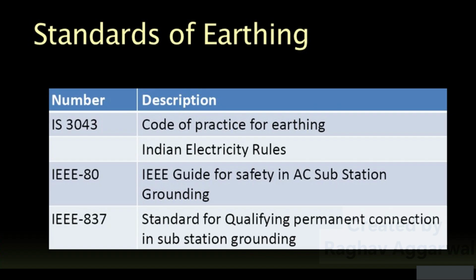You may refer to some of the standards applicable for earthing. IS 3043 mentions the code of practice for earthing. IEEE 80 provides the IEEE Guide for Safety in AC Substation Grounding, and IEEE 837 refers to the standard for qualifying permanent connection in substation grounding.